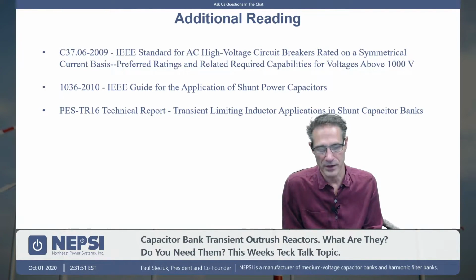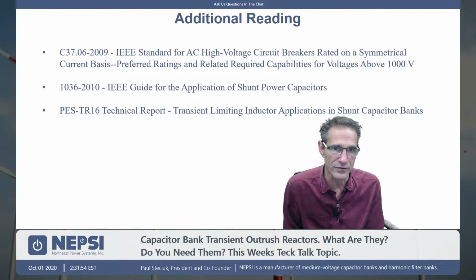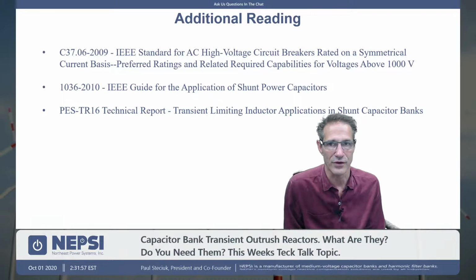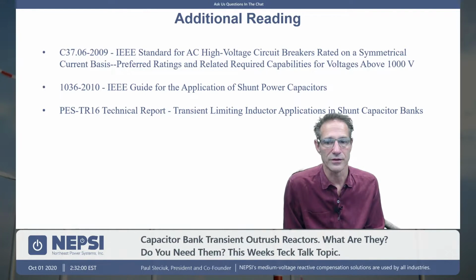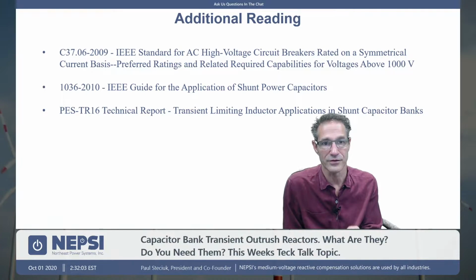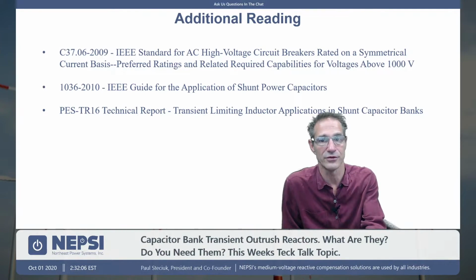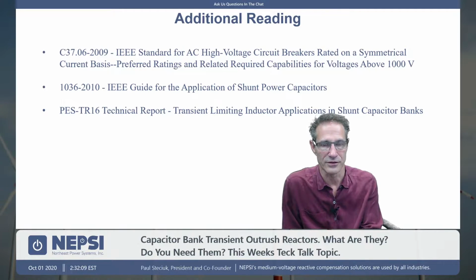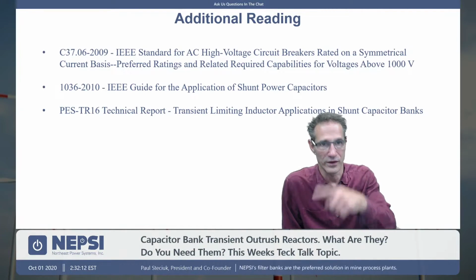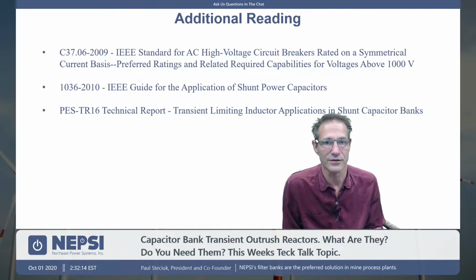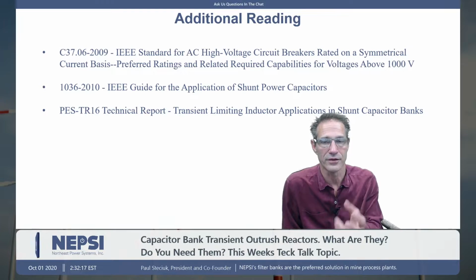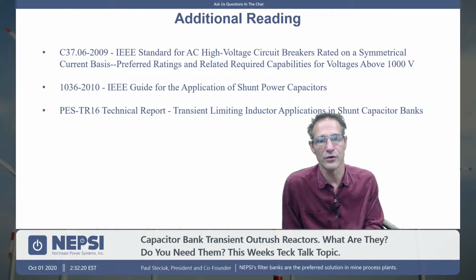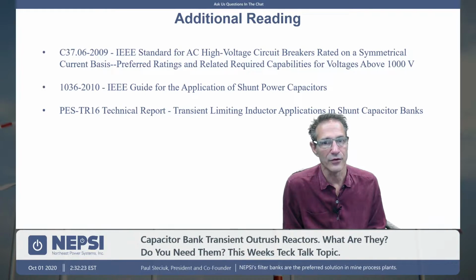Because remember, an iron core reactor that you use as a filter is different than the reactor that you would use for outrush. So you have to make sure that the iron in the outrush reactor does not saturate for the outrush current. You have to be able to conduct that current. You want to make sure that the inductance is linear through the full wave shape of that outrush current. Otherwise, you lose your inductance and you lose the effect of the iron that makes up that iron core reactor. So good question. You have to be very careful. Air core reactors are easier because there is no saturation concern. So we typically move in the direction of air core reactors and not iron core reactors.